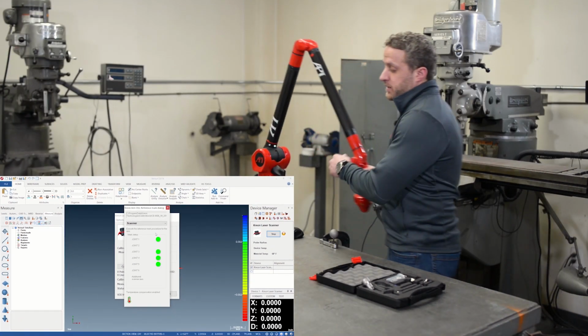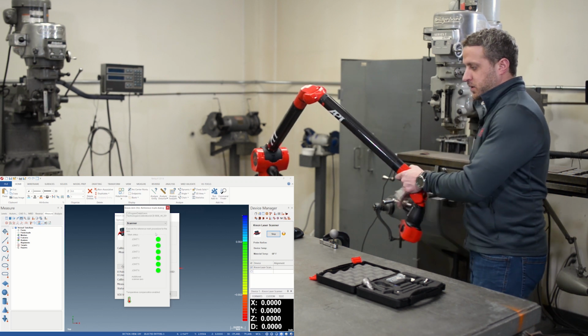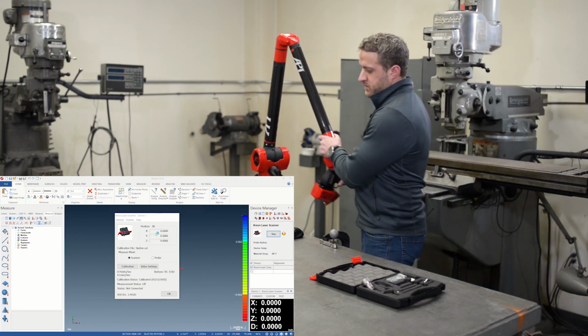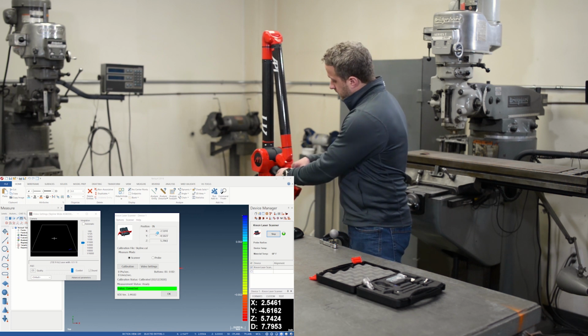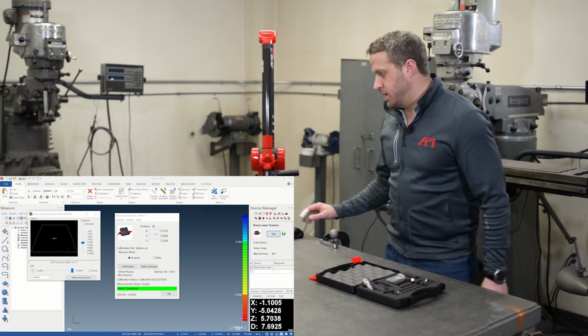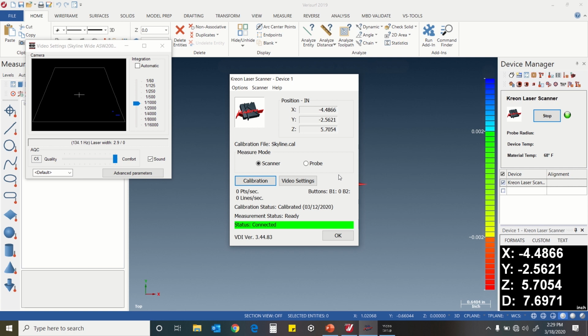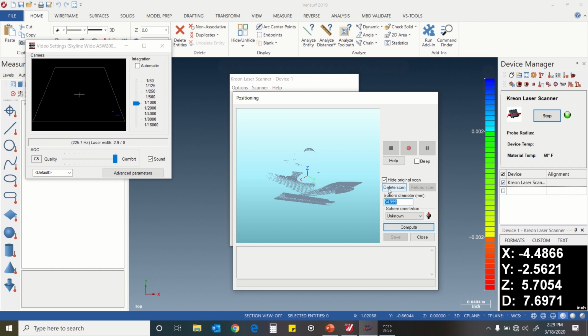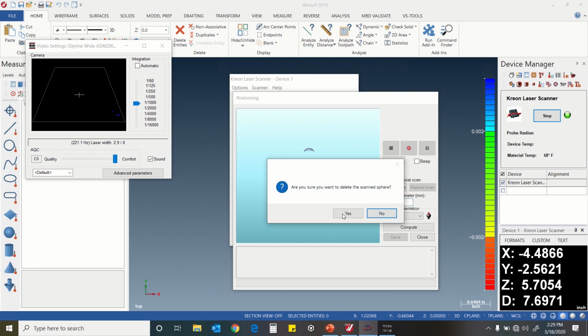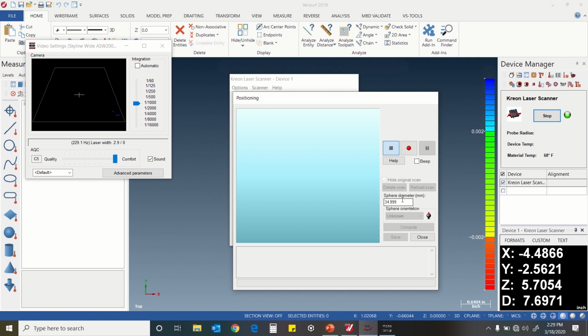Again, we're going to unstow it and exercise each axis, including the scanner axis. And now we are connected. So now that the arm is started, in our device controls, we're going to hit the calibration button. I have a previous scan in there, so I'm going to delete it out. And then it asks us here to put in the nominal diameter of the sphere, which is written on the side. That's 34.999 millimeters. When we're ready to record, we're going to hit the record button.